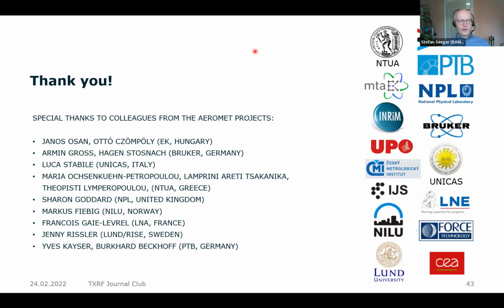We worked on that for more than half a year with our spectrometer to make sure that we are properly centered with our sample in the geometry. If we do not do that, we have severe effects on the quantification. But if we do it very carefully, the effects can be reduced to less than 8%. That is, in my opinion, a quite nice result at the moment. Perhaps we will be even better in the future, but 8% is something I can live with.